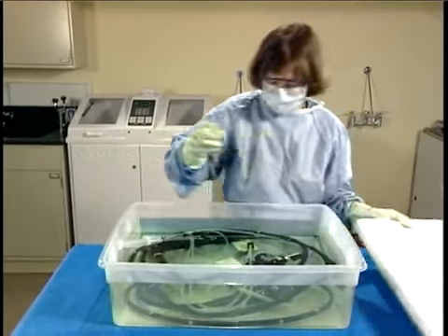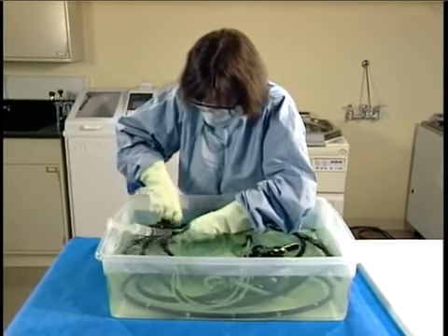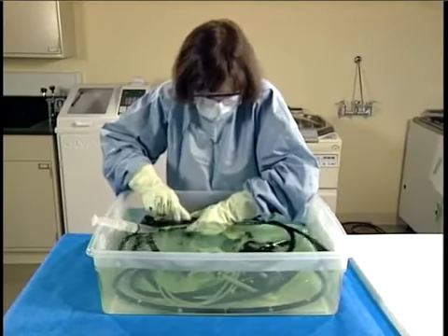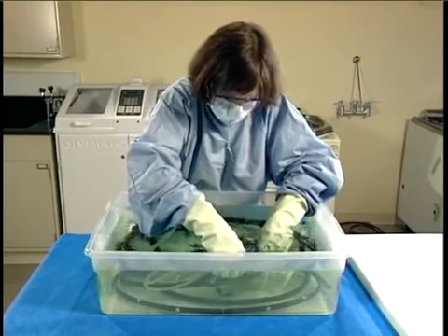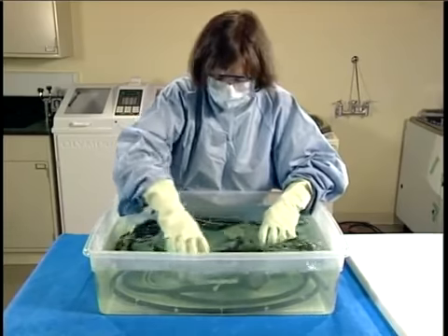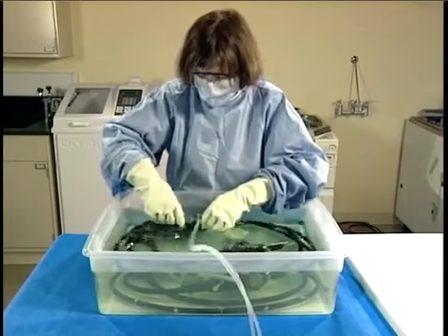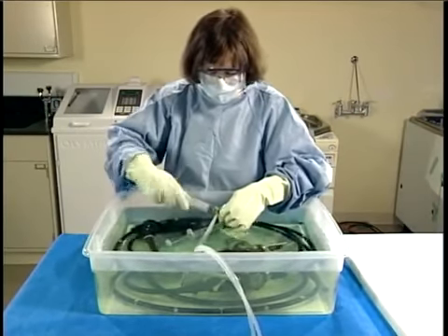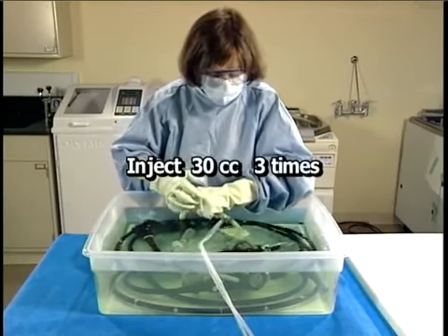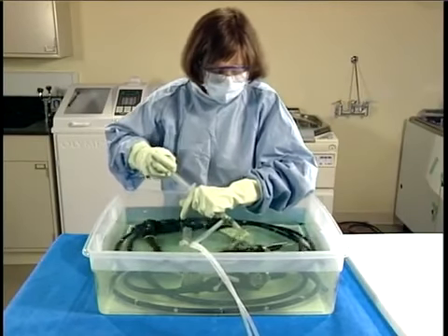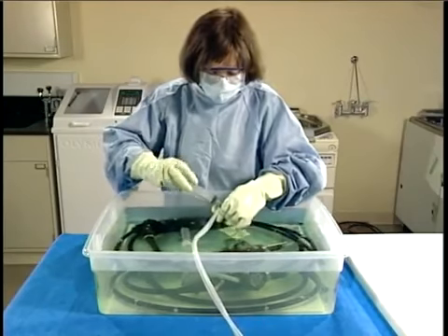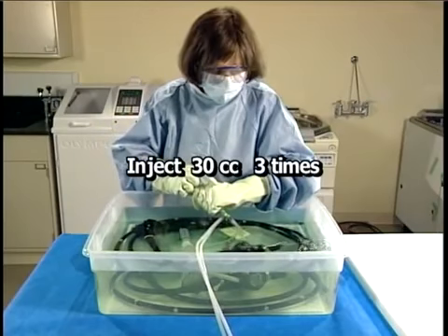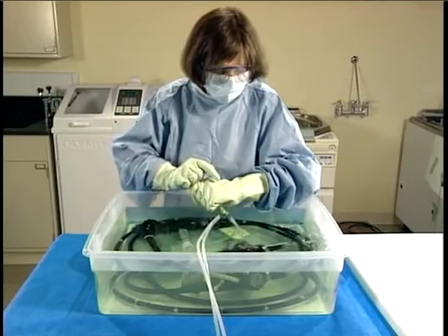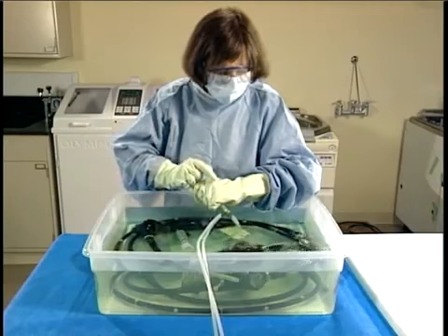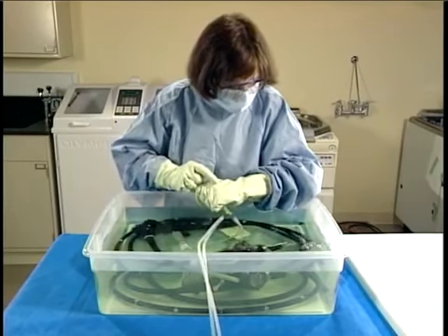After soaking the equipment in the disinfectant solution for the recommended period of time, reconnect the reprocessing accessories to the endoscope. Remove the intake filter from the disinfectant solution so that it will pick up air. Connect a sterile syringe to the air-water channel port and pump at least 3 times to expel the disinfectant from the air-water channels. Move the syringe to the suction port and pump at least 3 times to expel disinfectant from the suction channel. At the end of the process, you should observe air bubbles exiting the channel openings.